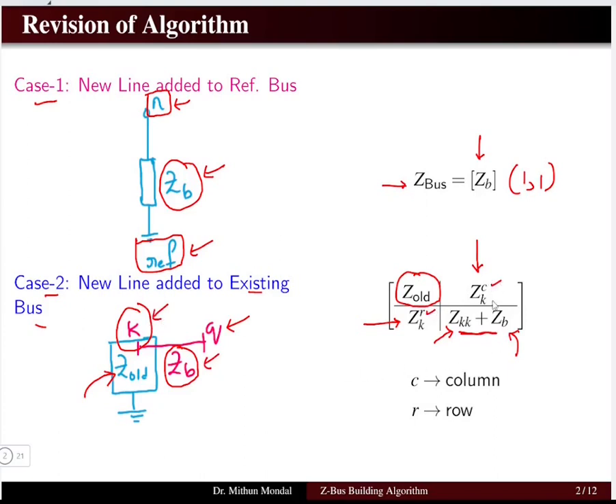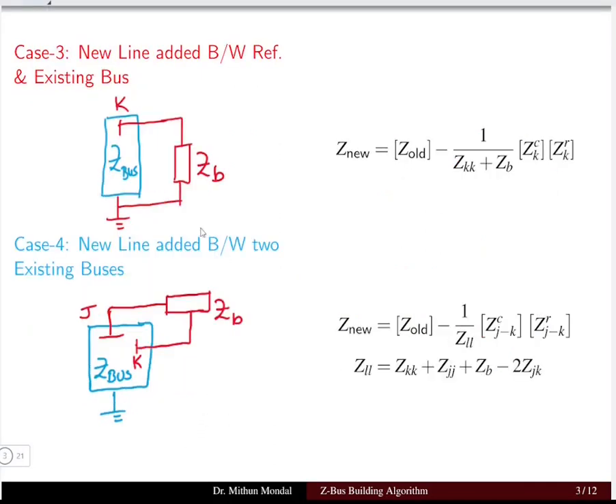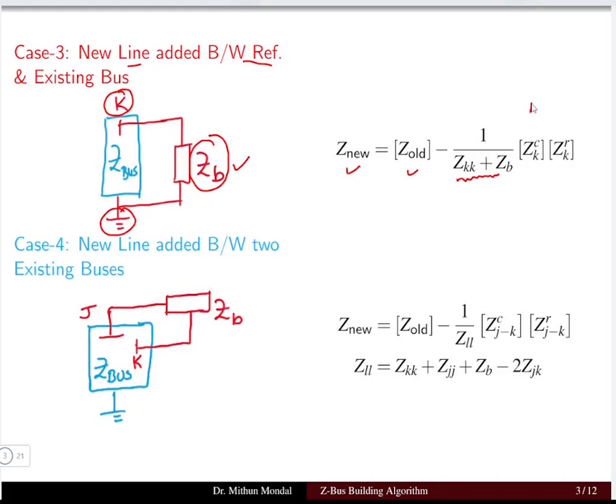Case 3: if a new line with impedance Zb is added between the reference bus and an existing bus k. In that case, the new impedance matrix equals the old impedance matrix minus one divided by (Zkk + Zb), multiplied by the product of the kth column and kth row elements of Z_old.